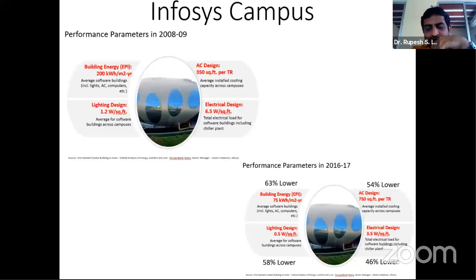Then we have the Infosys campus here. I think the numbers speak for themselves. Parameters in 2008-9 were these, and in 16-17 were these. On the EPI side, it was almost 63% lower. Again, it's not net zero energy, but very highly efficient. On the EPI, from 200 units of power, it came down to as low as 75 units of power per meter square. The AC went from 350 up to 750 square feet per ton. The electrical design came down from 6.5 to 3.5 watt per square feet.